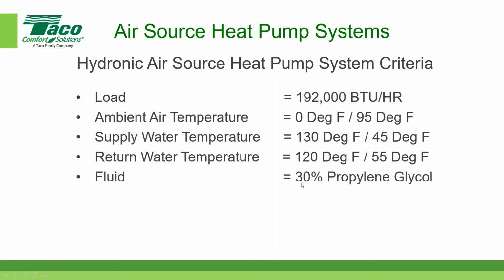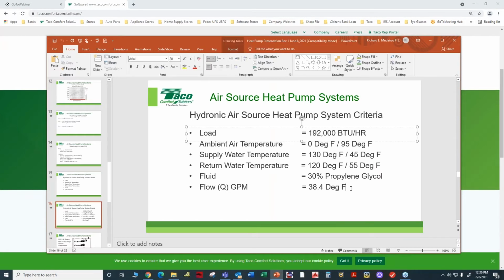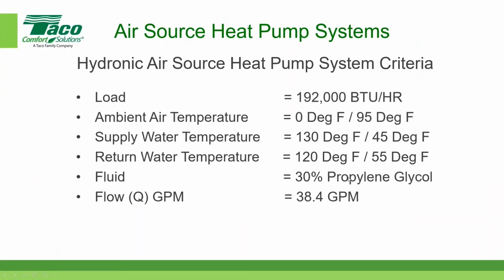The fluid in this case is 30% propylene glycol, because remember, our unit is an air to water heat pump. It's sitting outside in the weather, and the water glycol solution is outside. To keep the fluid from freezing, that's why we use the propylene glycol. And we've estimated the flow to be 38.4. I'm sorry, the flow. I messed that up, Brett. I put the units in there as degrees Fahrenheit. I'm going to fix it in real time here. GPM. Awesome. How's that? William will be happy. So when we look at this later, we say, whoa, geez.